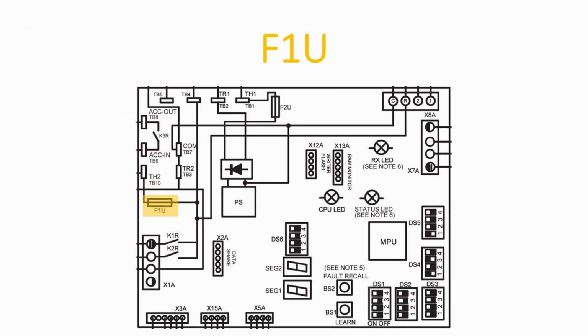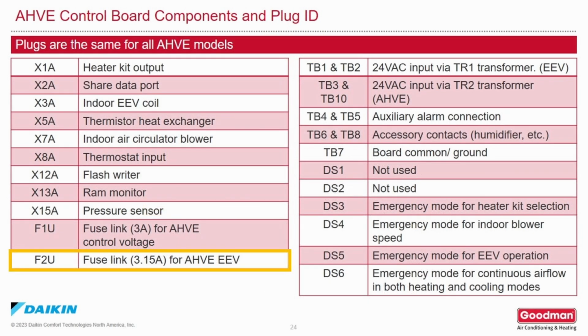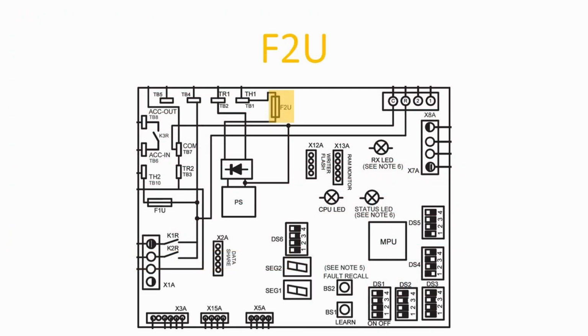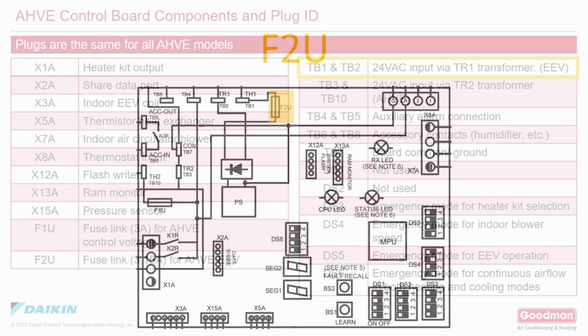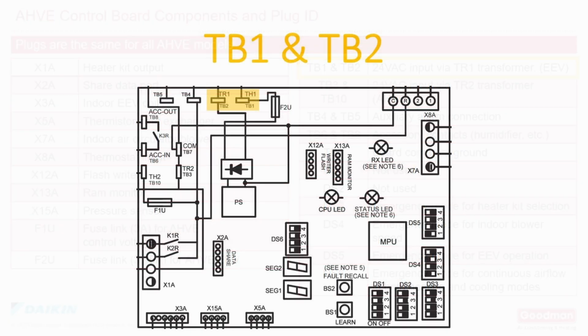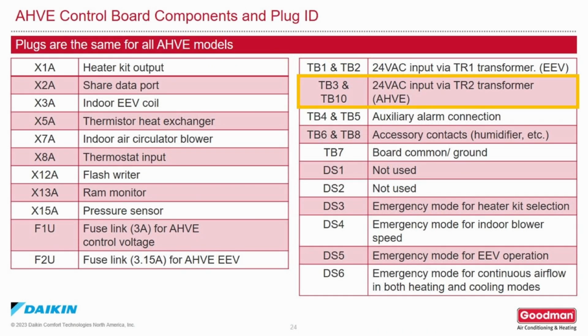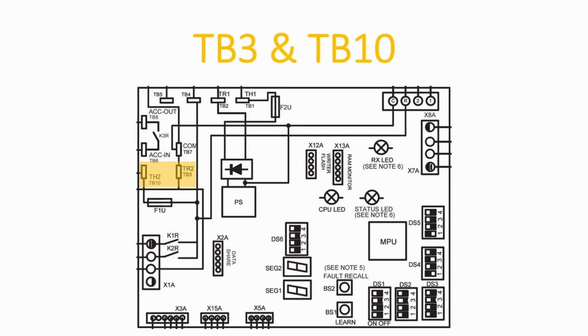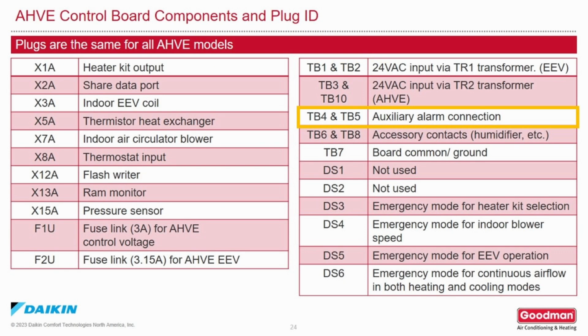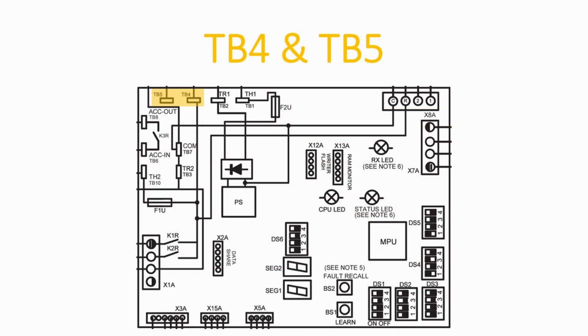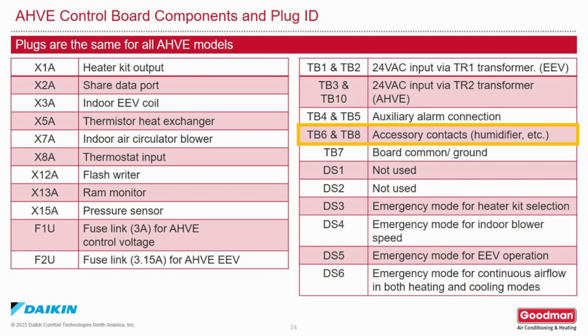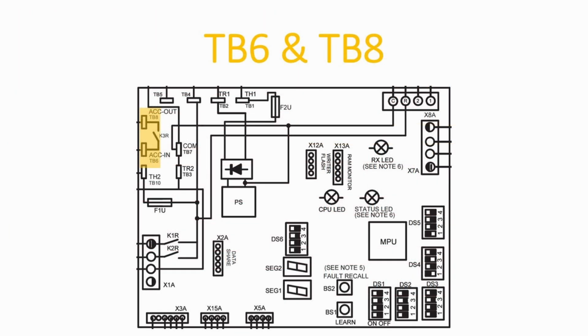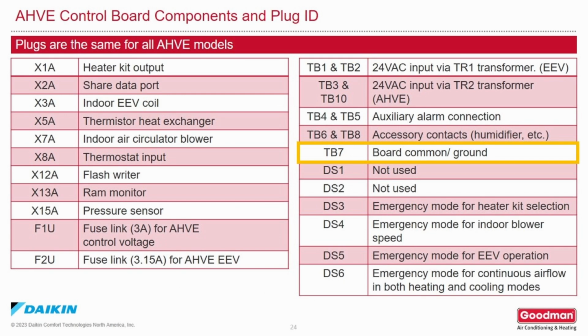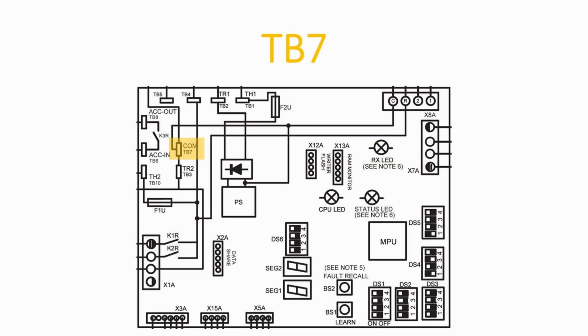F1U is a 3 amp fuse for the control voltage. F2U is a 3.15 amp fuse for the EEV. TB1 and TB2 are the 24 volt input via TR1 transformer for the EEV. TB3 and TB10 are 24 volt input for the transformer TR2. TB4, TB5 are auxiliary alarm connections. TB6, TB8 are auxiliary contacts for humidifier, etc. TB7, common ground for the board.